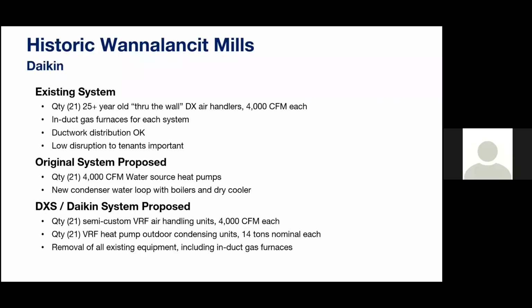So the next option, and the option, of course, which went forward, and what we're here to talk about today, is the VRF systems. So the alternative to that entire water loop with water source heat pumps was to provide VRF air handlers tied to the fully inverter variable speed VRF condensing units. So with this building, we have single zone systems with long ductwork runs and large capacity units. So what Jason touched on, we have our standard off the shelf VRF indoor units that can easily tie to the VRF condensing units. The only thing is that with these, we're limited by tonnage and by static on the fans to push the air to the space.